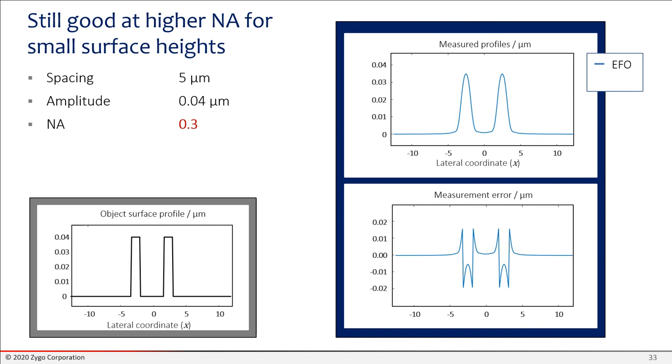The results look still good at a higher NA as long as the surface heights are pretty small. So here we have a numerical aperture of 0.3 and we've got two posts and they're short posts. They're 40 nanometers tall. And what we see with the EFO modeling is that these posts will not be perfectly rendered in a measured topography that you would expect. They're a little bit blurred. And if you overlay the results from the three-dimensional model, the more realistic model, you see again very good agreement. So that's great. So at a larger NA, as long as the surface heights are small, we're in good shape.